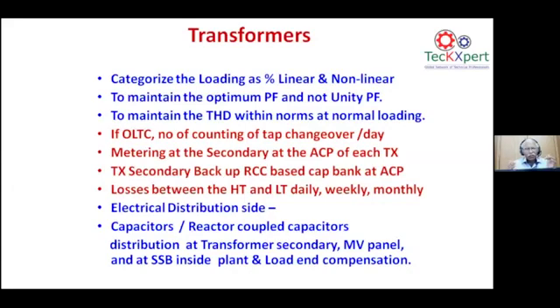The metering of the HT side and secondary side will show the daily, weekly, monthly transformer loss for your industry, and this can be monitored. These are all problems identified by condition monitoring, with in situ measurements and portable measurements. So the loss between the HT and the LT varies, and it can be seen for a week, on the working days and on the weekly holidays also, what is the condition of the transformer losses, and this can be assessed and analyzed.